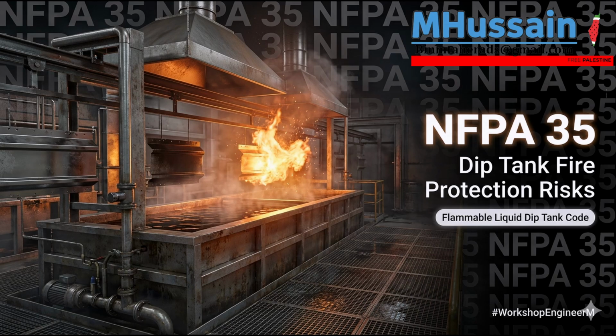Keeping it in a solid stream. Right. This keeps the flowing liquid in a solid, continuous stream, eliminating the free-fall droplet separation and drastically reducing static generation. Furthermore, the bottom of that fill pipe is often designed with a 45-degree angle cut to ensure the liquid flows smoothly across the bottom of the tank rather than jetting forcefully against the floor. It is such a beautifully simple mechanical pipe fix to neutralize a complex, invisible electrical hazard.